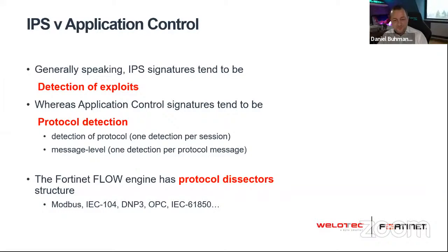You can go down to the message level as well as the arguments in the messages. We use our so-called protocol dissectors for substation protocols like Modbus, IEC 104, DNP3, OPC, IEC 61850, so our firewall understands all these protocols and lots more. The dissector is a function that understands these protocols in TCP/IP, because for example an IEC 104 packet can consist of one IP packet or multiple IP packets, and the dissector in the firewall will put all these together and understand that these packets are IEC 104, and this is the message being sent.